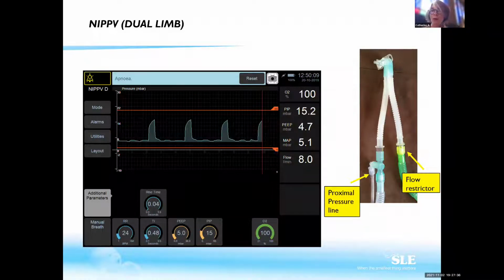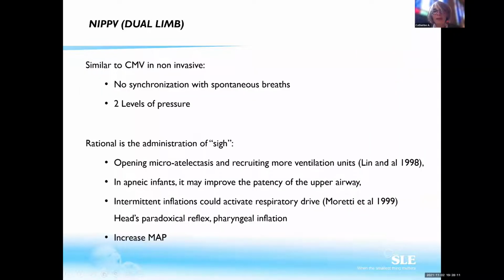Now, what you will see more and more in the ventilator is that we use NIPPV. NIPPV is exactly like the CMV that you had in ventilation, but in non-invasive ventilation. It means that we will be at the CPAP level, and from time to time we will deliver some breaths to the patient. So again, you will have to set how many breaths you want to deliver to the patient. You will also have to set how much PIP you want to deliver and the inspiratory time. So what do we expect from the CMV when we use NIPPV?